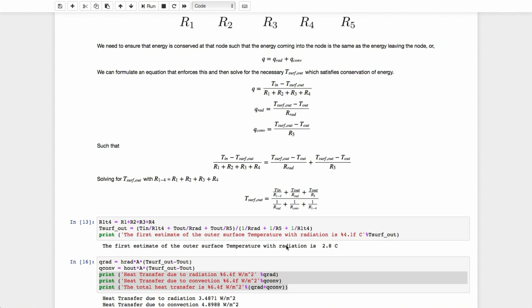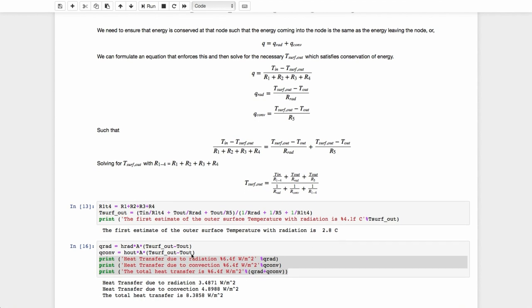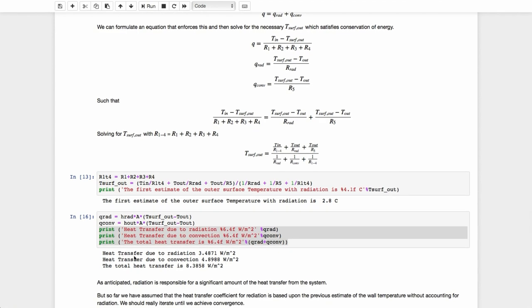then I can see that the first estimate of my outer surface temperature accounting for radiation is 2.8 degrees centigrade. And now I can calculate what the convection and radiation heat transfer is going out. And now I printed out the heat transfer due to radiation, which is 3.4871 watts per meter squared. The heat transfer due to convection is almost 5 watts per meter squared. And of course, the total heat transfer, or the Q, which is going through resistors R1, 2, 3, and 4, is 8.3858.